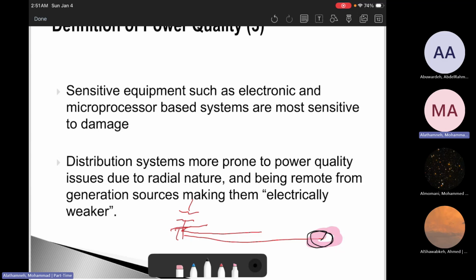Especially with long rural feeders, which we have a lot of in Jordan, at the edge they have a noticeable voltage drop and deeper sags during faults. When there's a fault, there will be a very big, significant voltage drop. Maybe the fault is not at your side but at other customers, and you will still be impacted by it. Big motor starts, like motors, pumps, and compressors, have high startup currents, and capacitor switching can also produce some impacts.